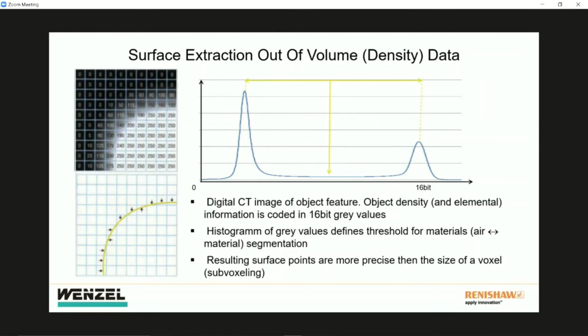One step before I talk about the proof, there is another thing. As it comes to image processing, I have to talk about resolution. So we strongly separate the accuracy in terms of a metrology result from the resolution of a scan, because the resolution has to do with the size of a voxel. On the left-hand side, let's imagine we have a very tiny object on a piece of square paper on the table, and our object is smaller than the grid. So our CT scan result will smear out the size and the shape of the object among several voxels, and in addition, the material density value is not preserved.